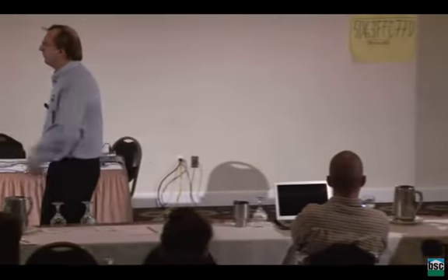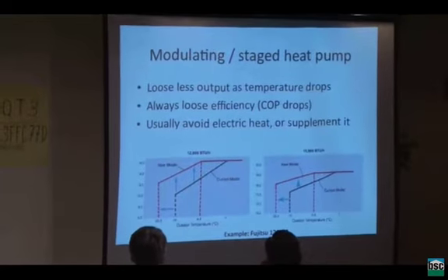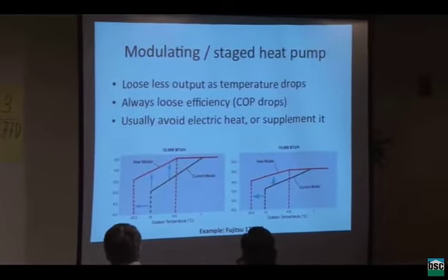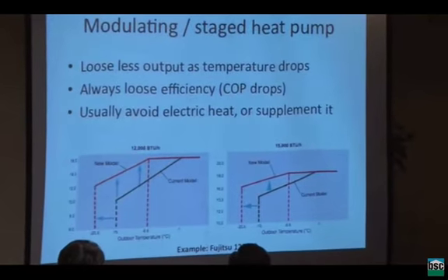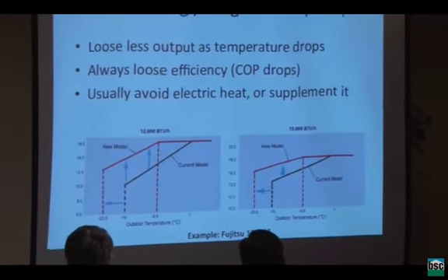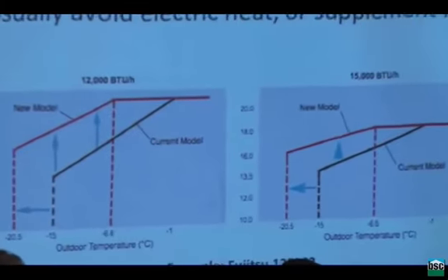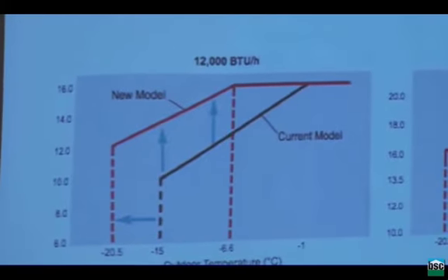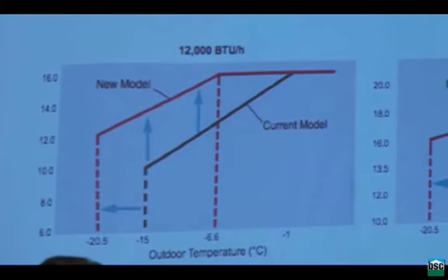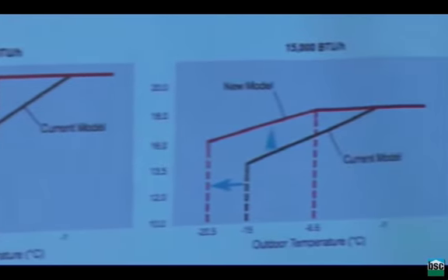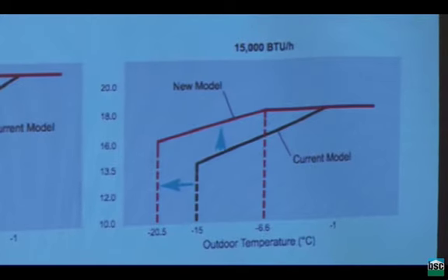Now, since that report was done on those products, the Fujitsu one has gotten better, and now the model on the left-hand side there is rated at 12,000 BTUs an hour. It's called a 12,000 BTU hour product. It produces 15,000 BTUs an hour of heat until the temperature drops down to about 20 degrees, and it's still producing 13,000 BTUs an hour at a little below, I think, minus 5 degrees Fahrenheit. So that's the kind of rating system I like. Call it 12,000 BTUs an hour, and it works at least at that level or higher over its entire range.